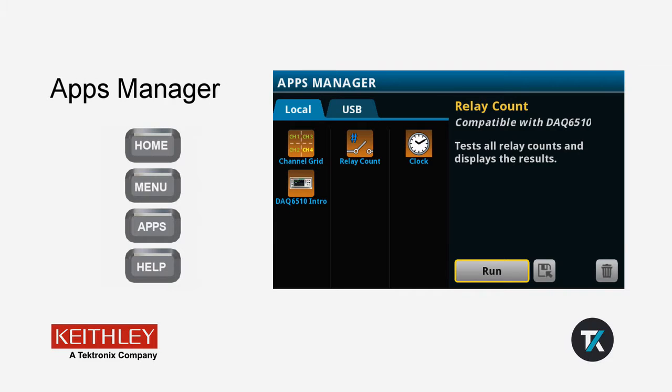The Keithley DAQ6510 introduces a new way to interact with your instrument using applications. These apps can be downloaded from the Tek website, installed on your instrument using a USB flash drive, and accessed in the Apps Manager by pressing the Apps key on the front panel. Two applications that are available on the instrument by default are the Channel Grid and Relay Count apps.